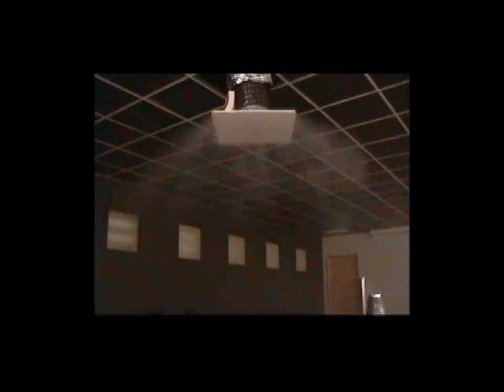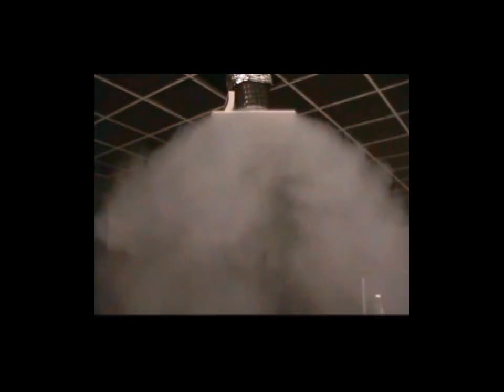So next let's look at the same perforated diffuser but dropped below the ceiling. So without the ceiling you can see that the air leaves the diffuser at about the same angle as the back pan, so the air just comes out at an angle and drops or dumps into the space. This would be uncomfortable if you're sitting directly below this diffuser.